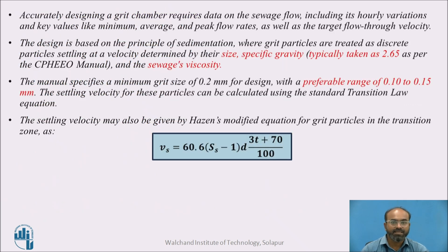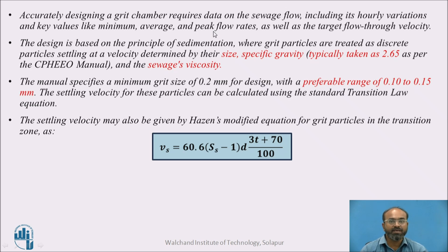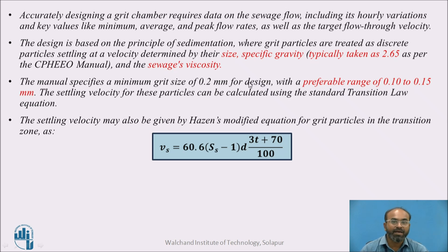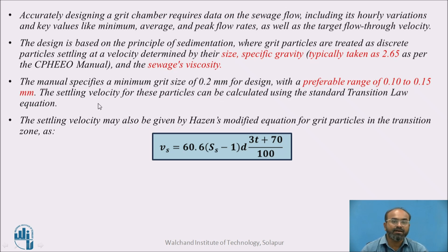When designing a grit chamber, I have to consider various factors like what the flow rate should be — whether minimum, average, or peak. Generally, peak flow rate is assumed for a grit chamber design. The design is treated as type one sedimentation where discrete particles settle, requiring consideration of grit particle size, specific gravity, and sewage viscosity. As per the manual, the minimum grit size is generally taken to be 0.2 mm, with a preferable range of 0.1 to 0.15 mm, and the settling velocity for these particles can be calculated using the standard transition law equation.